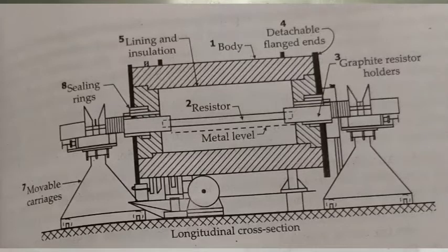It consists of a cylindrical shell with detachable flanged ends. For ease of lining, the furnace is designed to rotate on rollers. Part six is to enable the body to be rocked backwards and forwards. The refractory lining, shown by point 5, is built into the shell. To reline the furnace, the shell is lifted off and the rollers turned vertically on the end, the top end cover is then removed, and the lining material is rammed round suitable formers.